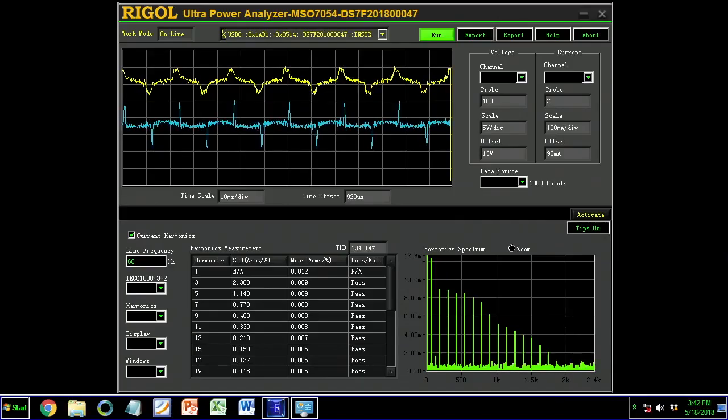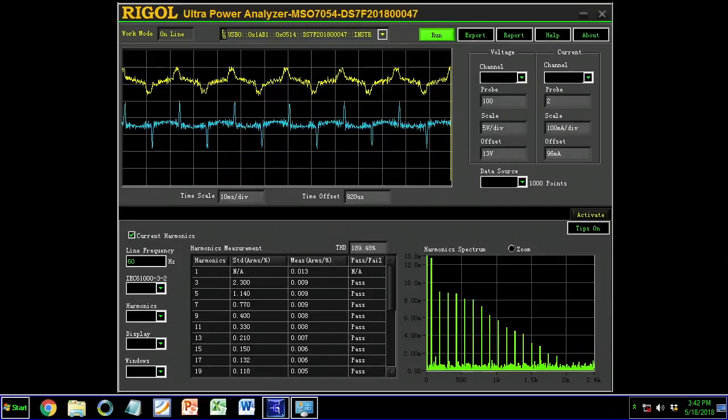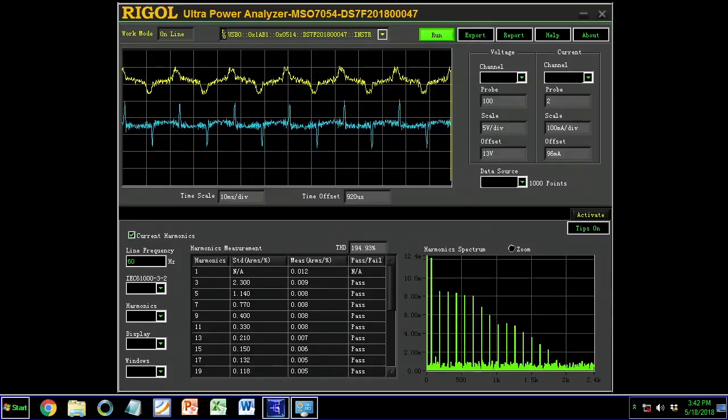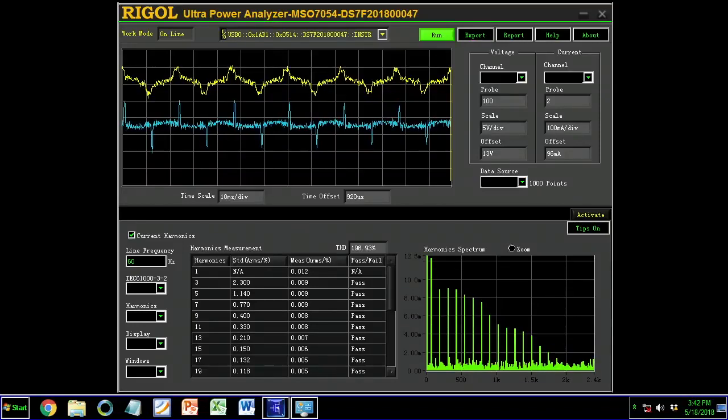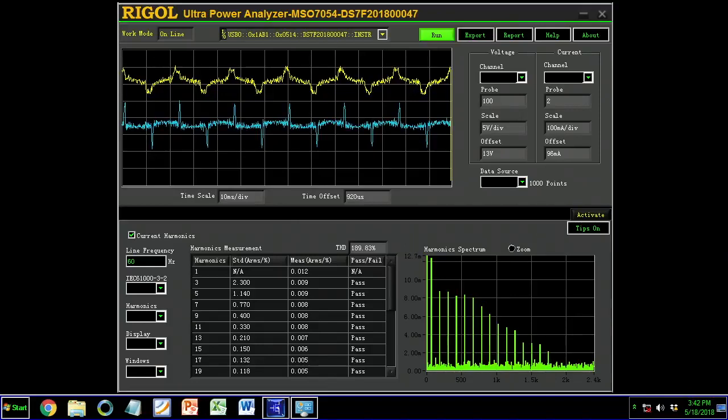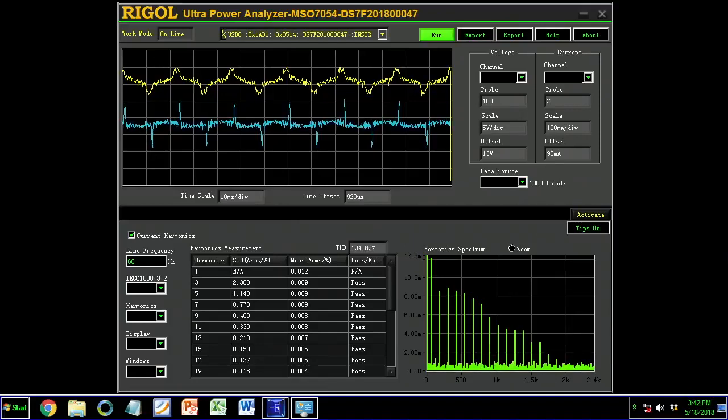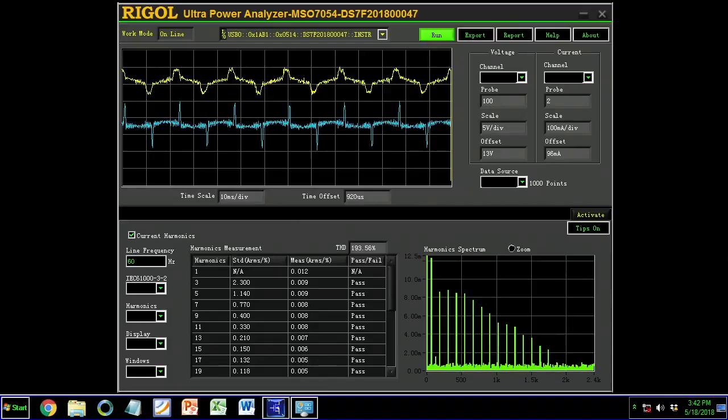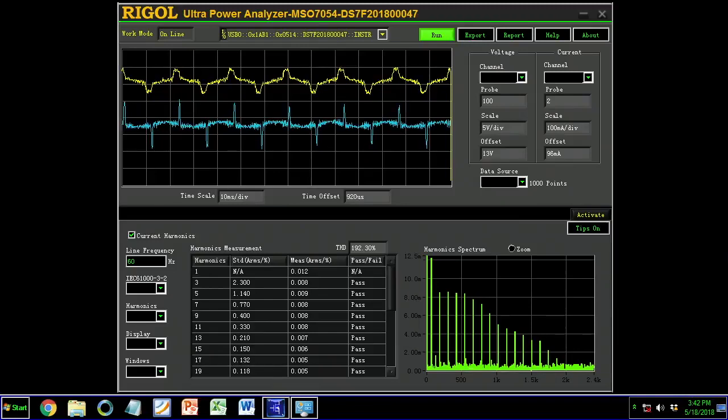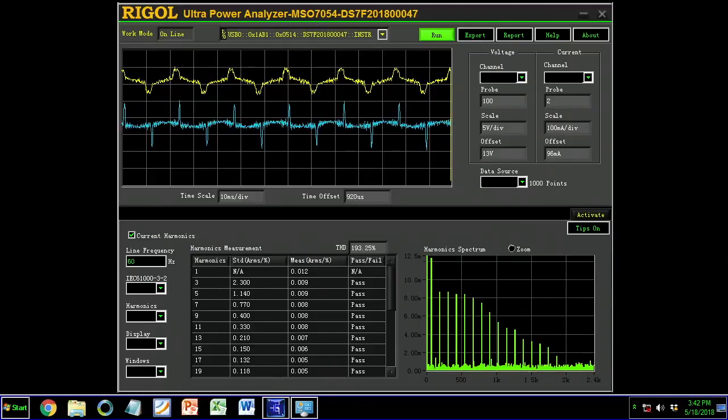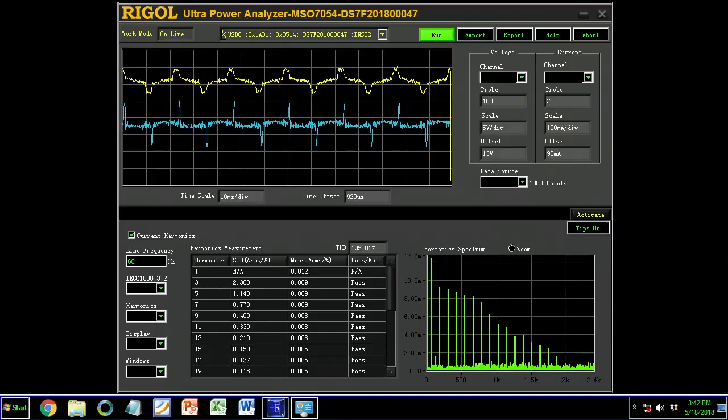Here the software is calculating the current harmonics within your signal by using both the voltage and the current measurements together. You can also do things like safe operating area and other measurements within the Ultra Power Analyzer software to give you a complete look at all your power analysis needs.